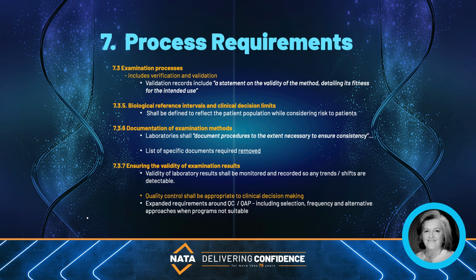Labs shall verify procedures, ensuring the manufacturer's required performance can be achieved before introduction to the extent necessary to ensure valid results. Staff with appropriate authorization and competence shall review verifications, and records shall include a statement of whether the performance specifications were achieved, and if not, what action was taken.